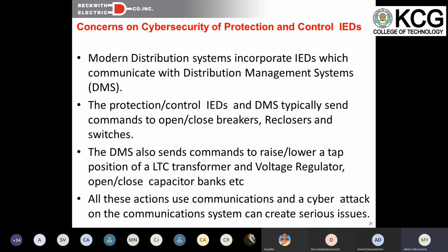If you're talking about a volt-var control system on a DMS, you may be talking to 3,000 capacitor banks and maybe 2,000 transformers on your system, trying to send commands to raise or lower tap changes, or open and close breakers, reclosers, all kinds of stuff.